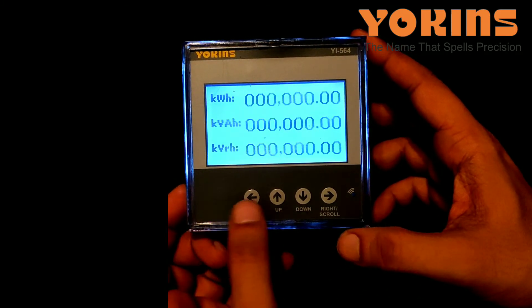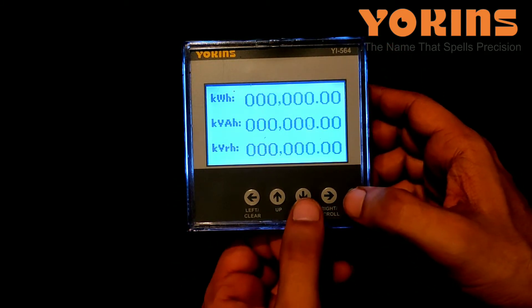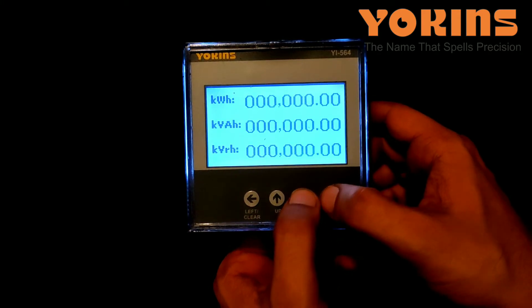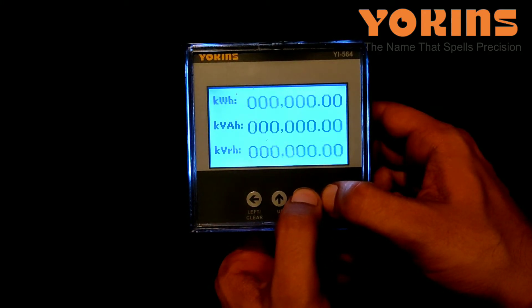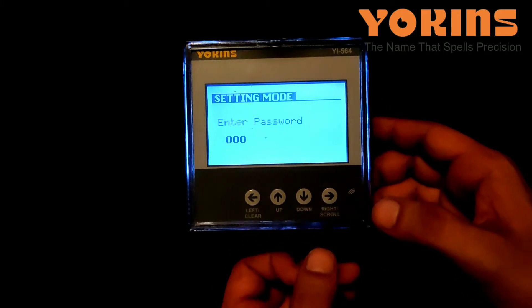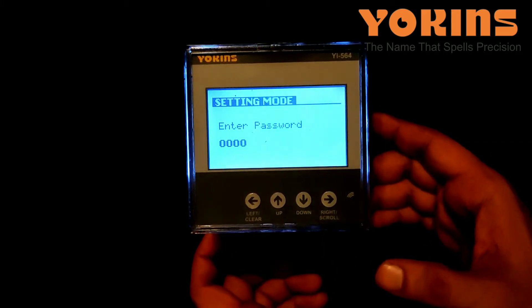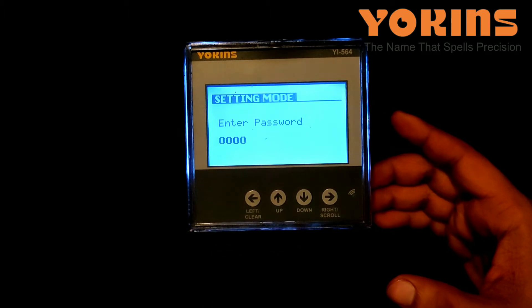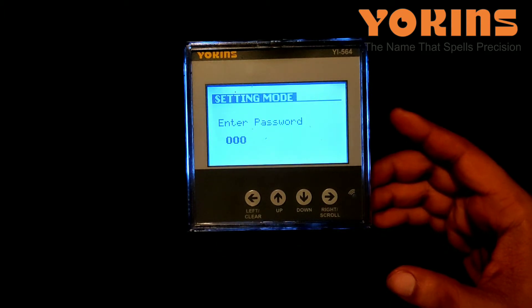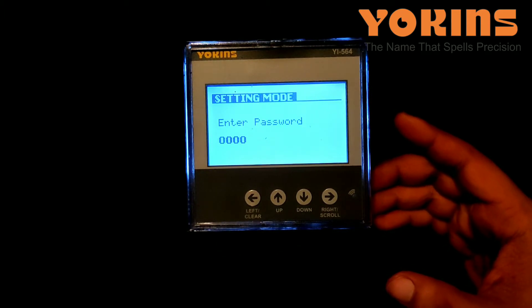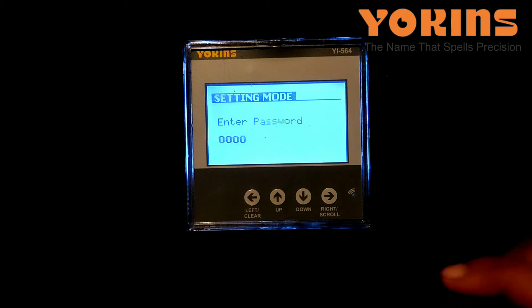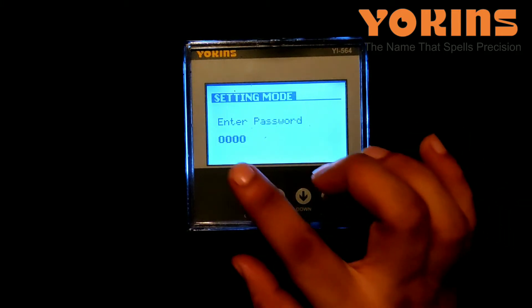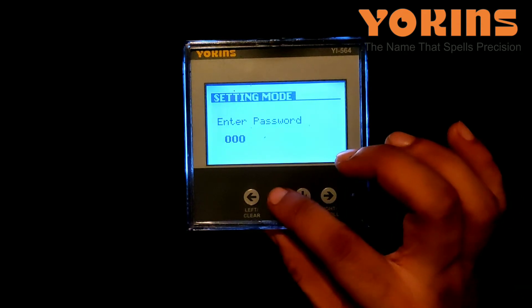To enter programming mode, we can see four buttons. We'll press the down button and right button together for a few seconds. Once we press it for a few seconds, we can see the first zero starts blinking — it's asking for the password. Our standard password is one thousand, so we'll enter 1000 to enter programming mode.